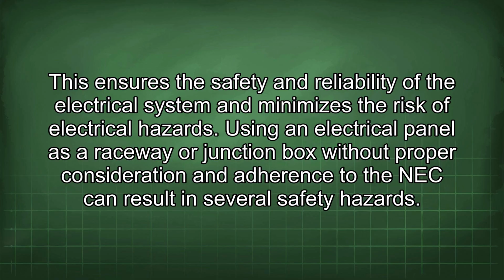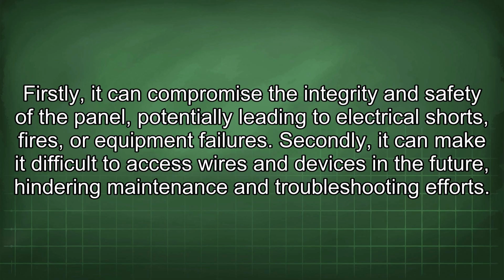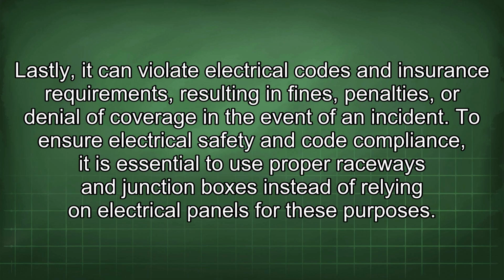Using an electrical panel as a raceway or junction box without proper consideration and adherence to the NEC can result in several safety hazards. Firstly, it can compromise the integrity and safety of the panel, potentially leading to electrical shorts, fires, or equipment failures. Secondly, it can make it difficult to access wires and devices in the future, hindering maintenance and troubleshooting efforts. Lastly, it can violate electrical codes and insurance requirements, resulting in fines, penalties, or denial of coverage in the event of an incident.